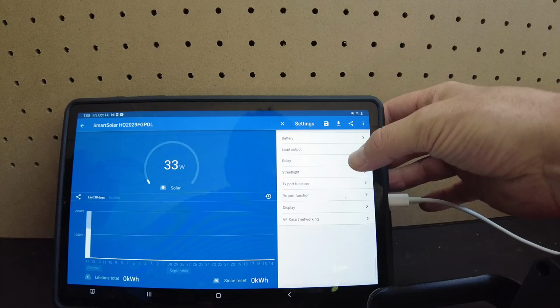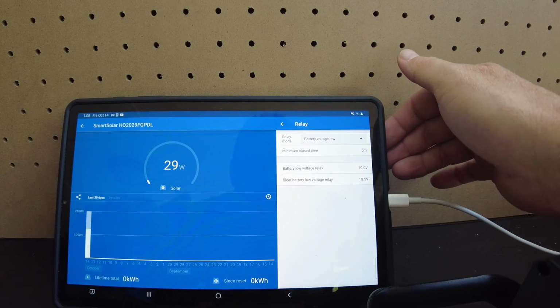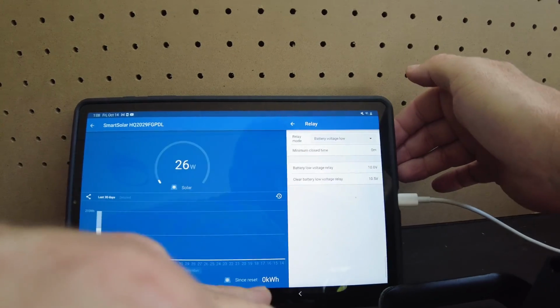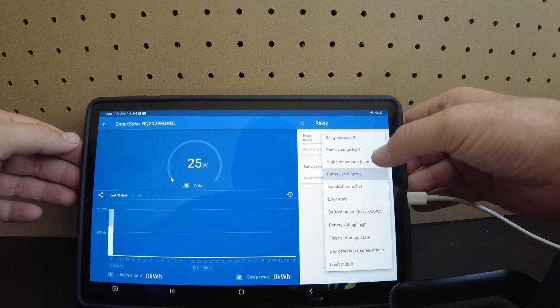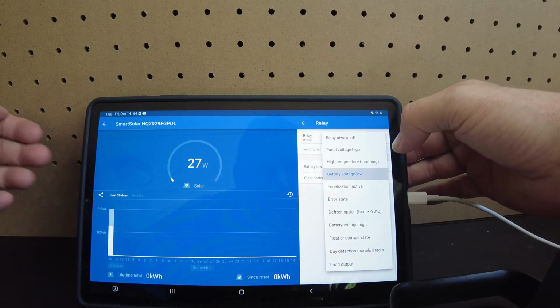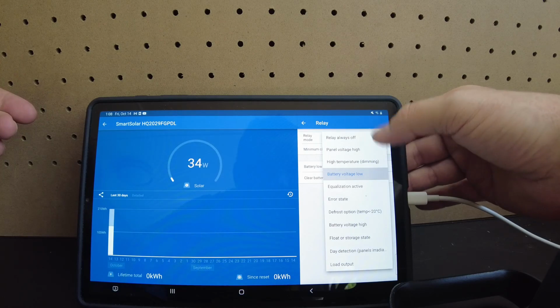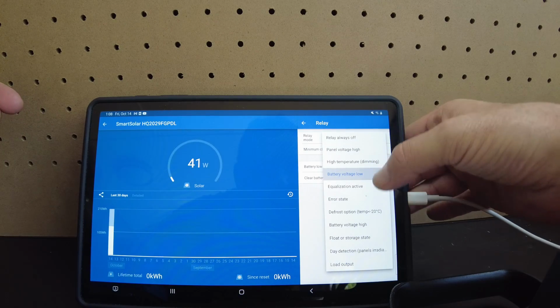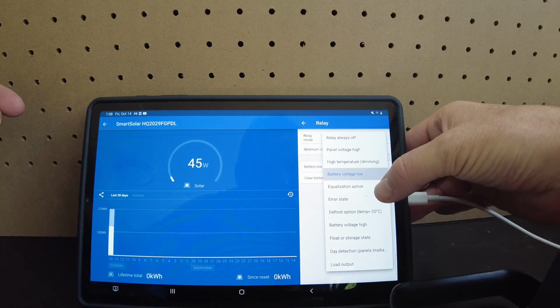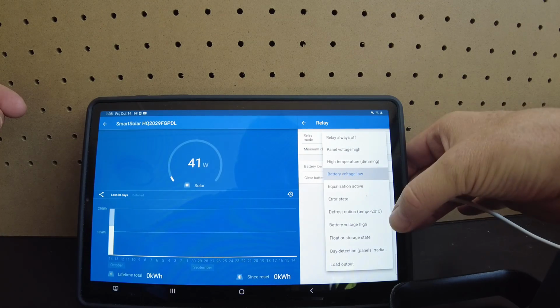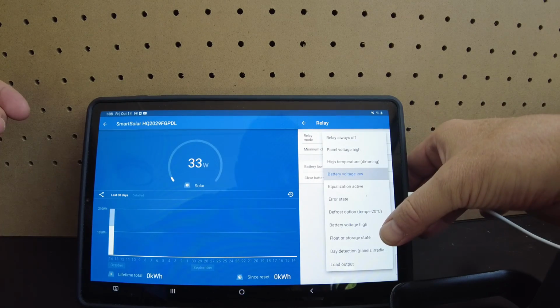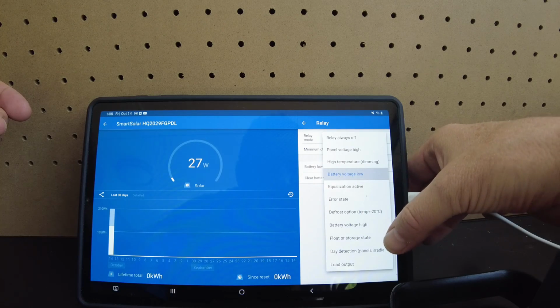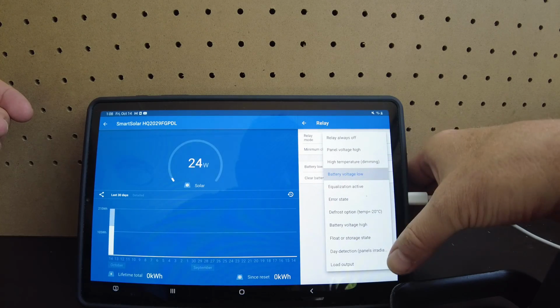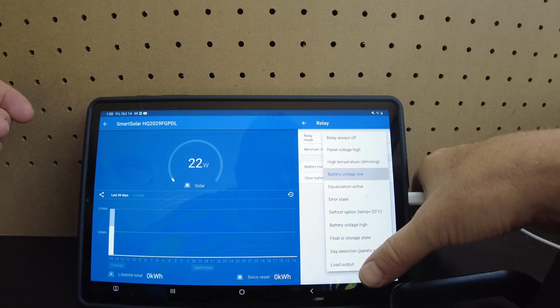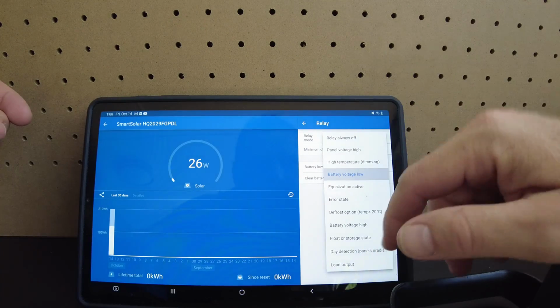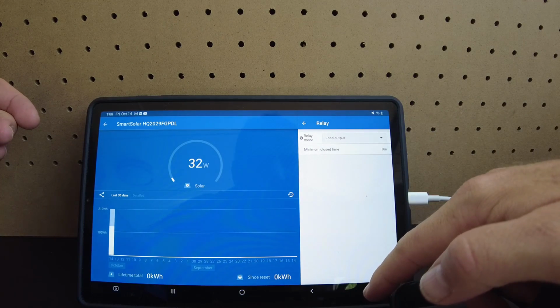Actually, no, it doesn't control it, because there's a relay right here. So you can set up the function of the relay - relay always off, panel voltage high, high temperature, equalization active, error state, defrost, battery voltage high, float or storage state, day detection, load output. Let's see.